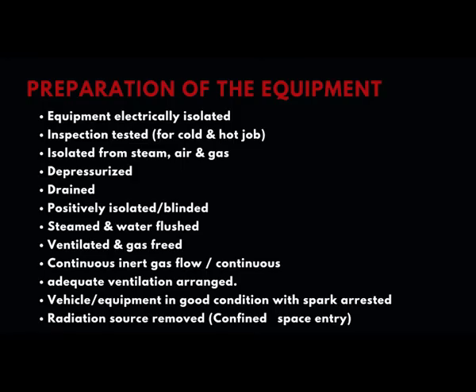As operating personnel, before giving the work permit, you have to ensure the preparation of the equipment is done as per standard operating procedures. For example, if a task involves a system connected to a pump, and the pump connected to a motor, the electrical equipment must be specifically isolated so the motor does not accidentally start the pump and create unexpected behavior inside the plant.